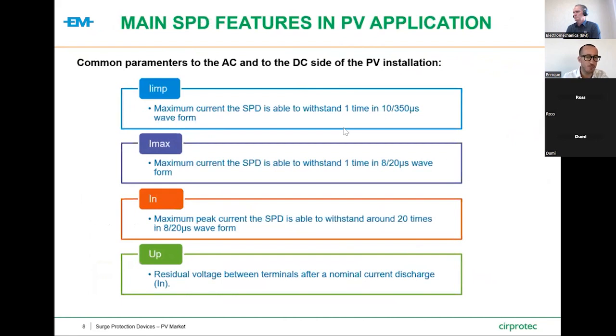It's not that easy to explain it right now. Perhaps with the presentation, I will forward it to you, Christo. You can share it with the customer, and if there is any further question, I can help to clarify. At the end, the waveforms are coming from the standards, and thanks to these waveforms, the standard sets up the parameters every manufacturer should fit to assure the SPDs are type 1, type 2, or type 3, according to the robustness once they are discharging current to earth coming from overvoltages. Okay. Perfect. Thank you for that.